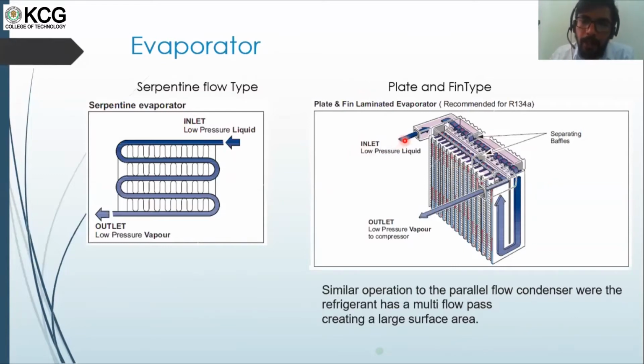So here your refrigerant will enter at low pressure and liquid state from the TXV. So once it comes over here, here is one baffle. So again, it will go down and come in this direction. Again, it will shift to the adjacent tube, but again, there is a baffle. So it cannot go to this compartment. Again, it will travel back, changing its direction. It will come over here. Again, it will travel to the end, and finally, this last circulation will happen and it will come out.